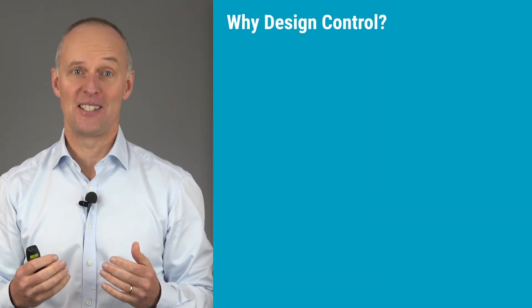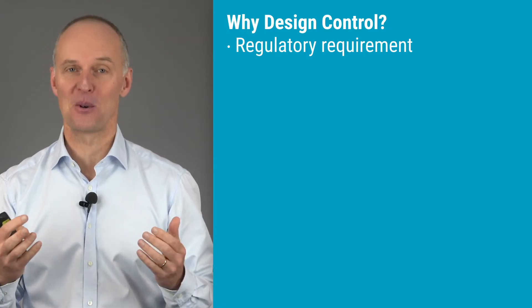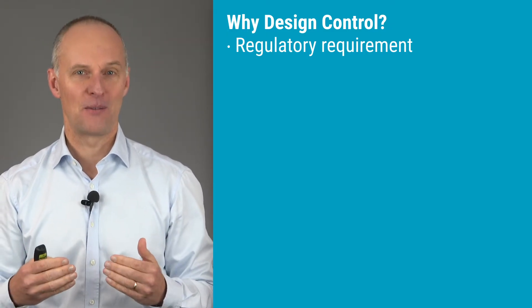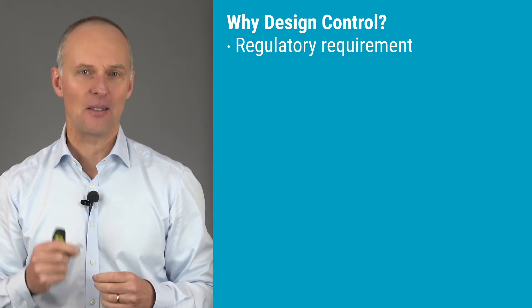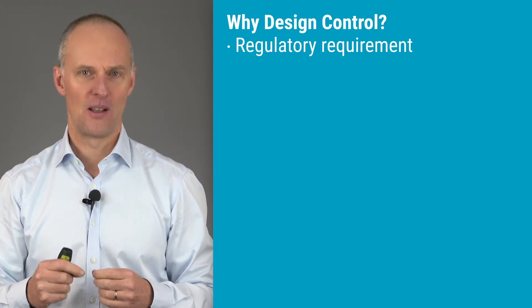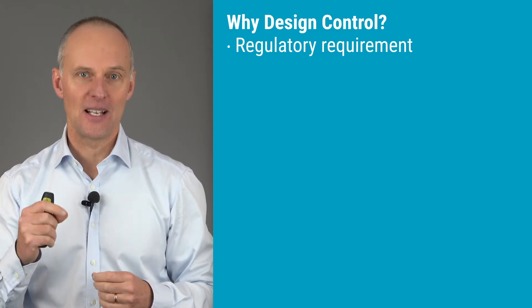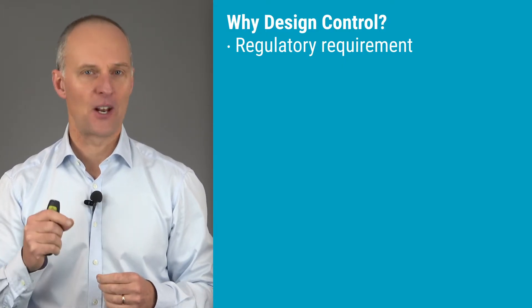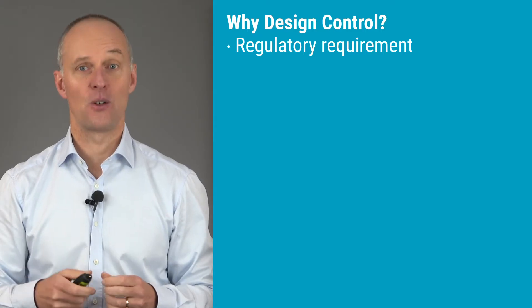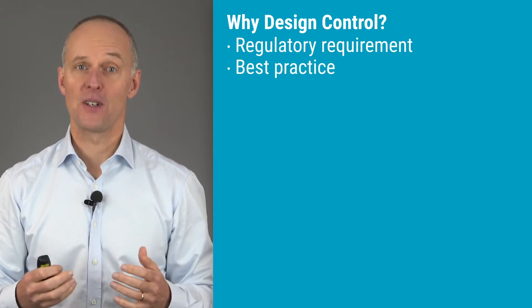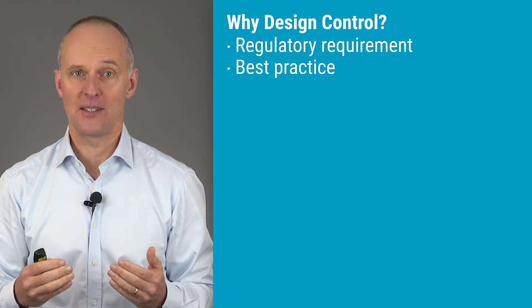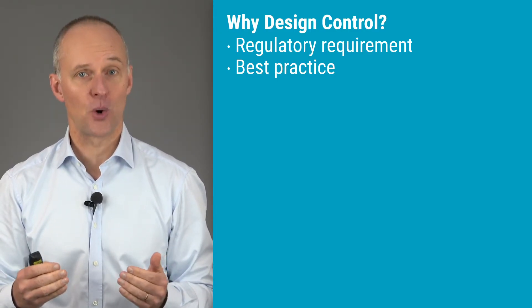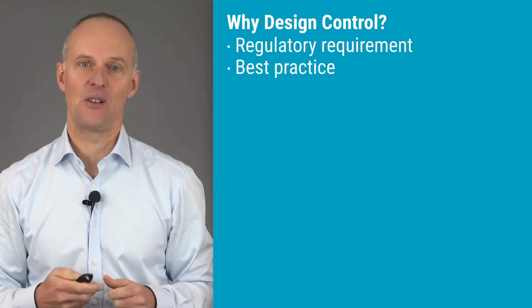The obvious answer to why we should care is that complying with design control requirements is a regulatory requirement. But if someone tells you that you should work with design control only because it is a regulatory requirement, I think that person has overlooked something very important. Working according to design control requirements is an effective way of creating products that are not only safe but that will also satisfy your customers' needs. Most design control requirements represent best practices in developing new products, and companies from other industries work according to these principles anyway because they see the value in it.